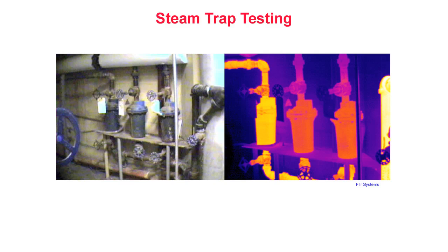In order to maintain steam system efficiency, condensate must be quickly removed from the steam system. In order to do this, an automatic mechanical valve called a steam trap is utilized to discharge condensate while retaining live steam within the system. In this image set, we see three inverted bucket traps. Referring to the thermogram, the trap on the left shows no apparent temperature differential across the trap. This may be due to cycling of the trap or a constant leak. Here, contact ultrasound can be used to confirm the trap's operating condition.